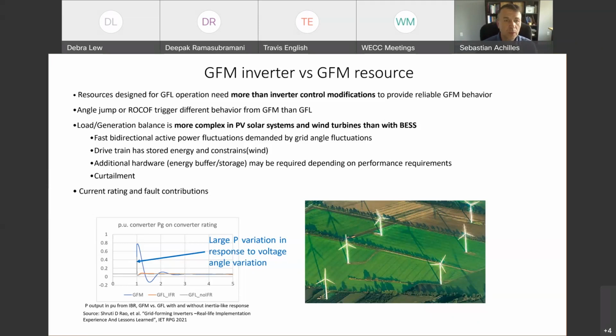So the picture on the left, taken from a paper led by Shruti Rao, shows the differences in response to an angle change. You perform an angle change in the grid, a voltage angle shift that could be, for example, because you operate transmission lines, which significantly modifies the power transfers. You can see that the grid following concepts basically do not modify the power output, while this battery has a significant increase in active power. That's the blue line, and that active power increase is very fast.